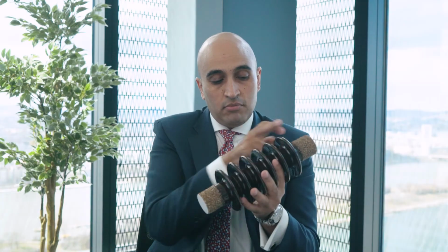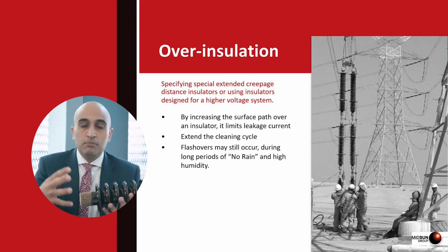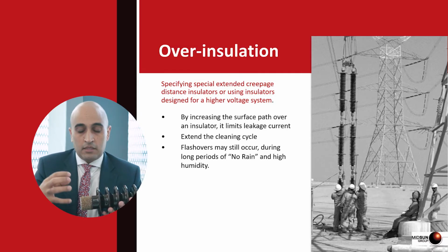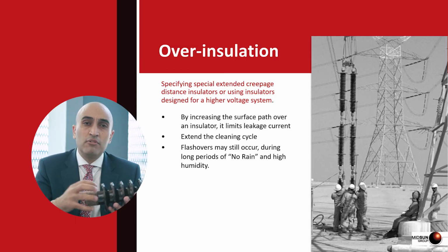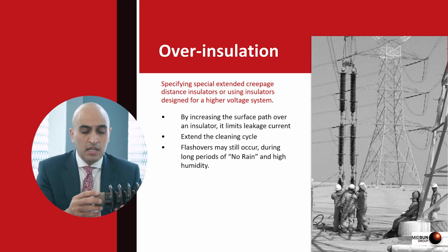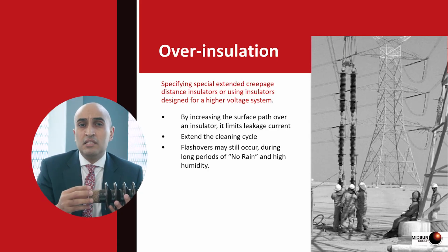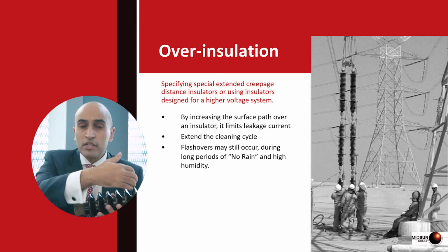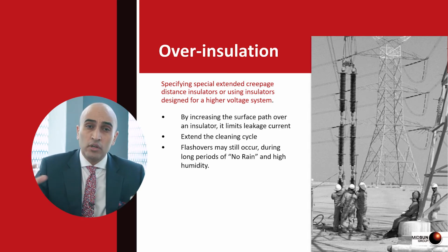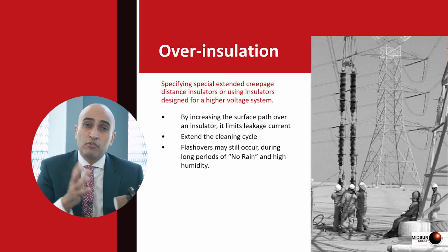The second approach of mitigating the problem of flashover on high voltage insulators is by modifying the design. What I mean is by increasing the creepage distance of an insulator. The creepage distance of an insulator normally is rated for the voltage that this insulator is going to insulate. However, some utilities have decided, as their mitigation approach of flashover, to increase this creepage distance. For instance, you can see here in Kuwait, the electrical utility is using more insulators per string in order to have longer or larger creepage distance to avoid flashover.